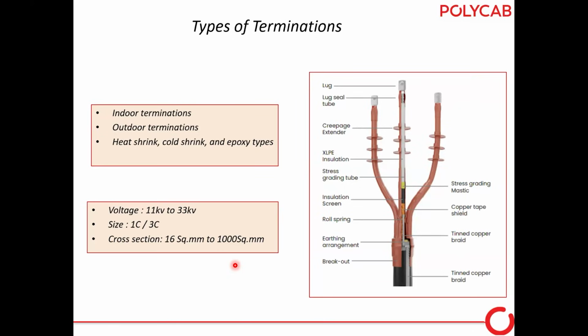Epoxy type terminations are a very old technology. Nowadays, no one uses epoxy type terminations, but heat shrink and cold shrink are generally used. Voltage ratings 11 kV to 33 kV, single core, 3 core, cross section 16 square mm to 1000 square mm. Again, what we saw in the LT termination, here are similar, some components are there.